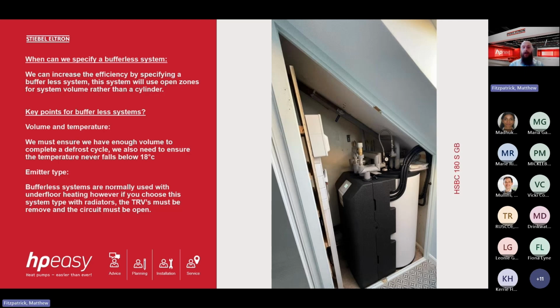You can also use bufferless systems when space is short. You haven't got enough area to install a buffer cylinder, but you'll need to keep an open volume. Now, for our larger units, it's 40 litres, and the smaller 7.5 kilowatt units, it's 20 litres of volume. So that's a couple of things to bear in mind, that we need to keep a set amount of open volume for the air source heat pump to be able to complete defrost cycles, and a minimum temperature of 18 degrees. And we can't mix and match heat emitter types. It must always be open loop and one type of heat emitter.